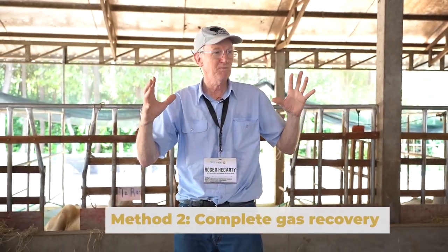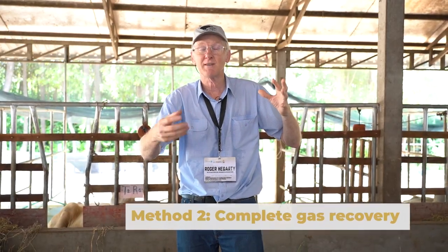But what we will move on to doing when we have better resources is to put a bigger cylinder on a bigger set of scales and release for a longer time just into the chamber with the door closed and the shroud folded up, to make sure there are no bad leaks out of the box itself, which we have not checked today. So there are two different things: a complete recovery test when the box is all closed up and there is just a little bit of air coming in through the collar or the shroud, in contrast to an analytical recovery test where we put it straight into the exhaust stream, which is what we've been doing today.